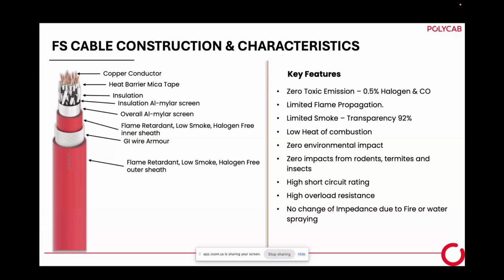Limited smoke. So transparency is 92%. Means if we burn this cable in a chamber, 92% transparency will be there. So 8% small smoke will be there, but 92% transparency means you can see each other, you can see the exit, you can see the staircase easily. People can move. Low heat of combustion. Here is a technology: when we develop the compound for the inner jacket, insulation, or outer jacket, when you burn this material, the heat of combustion is very low. So heat release is very low. So zero environmental impact. Environmentally, it is very eco-friendly, so the environment does not spoil. People breathing in this environment are safe.